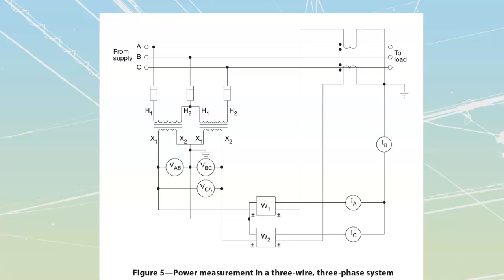and this is going to be for my total energy and power metering, where I've got everything connected. Now, we know that when it comes to our metering over here, we can get away with one less watt meter element than what we have for the load. So I've got VT and CT that are together going to feed onto a watt meter, which is then going to multiply my volts times my amps over here, and therefore it's going to give me my watts. Now this is a watt meter. It's not a VA meter or a VAR meter or anything like that, which means it's only going to tell me about the true power that is coming out. I'm also going to have to take a look at both of these and their ratios to figure out my apparent power, my VA, my power factor, all that other stuff.